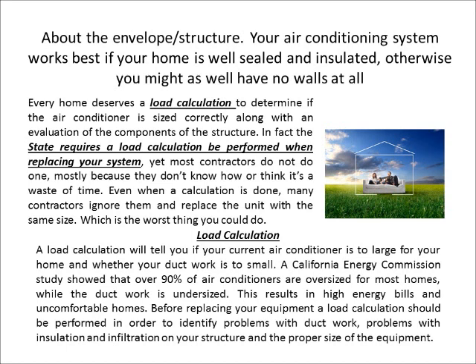The load calculation will tell you if your current air conditioner is too large for your home and whether your ductwork is too small. California Energy Commission studies showed that over 90% of air conditioners are oversized for most homes. With undersized ductwork, the duct work reduces the capacity of the air conditioner, and since the air conditioner is already oversized, it gets even more exacerbated, resulting in high energy bills and uncomfortable homes. So before replacing your equipment, a load calculation should identify problems with ductwork, insulation, infiltration of your structure, and proper size of the equipment.